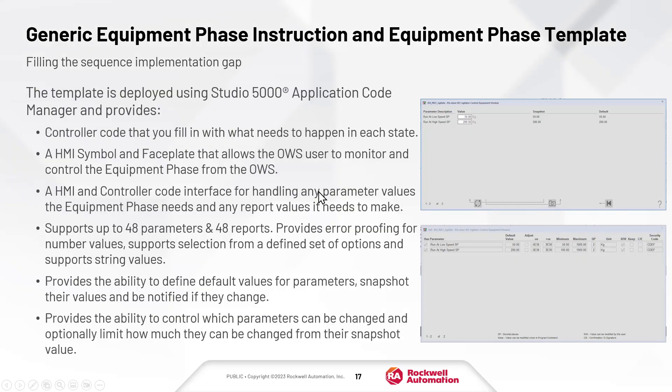The template is deployed using Studio 5000 Application Code Manager and provides controller code that you fill in with what needs to happen in each state, an HMI symbol and faceplate that allows the operator workstation user to monitor and control the equipment phase, and an HMI and controller code interface for handling any parameter values the equipment phase needs and any report values it needs to make.